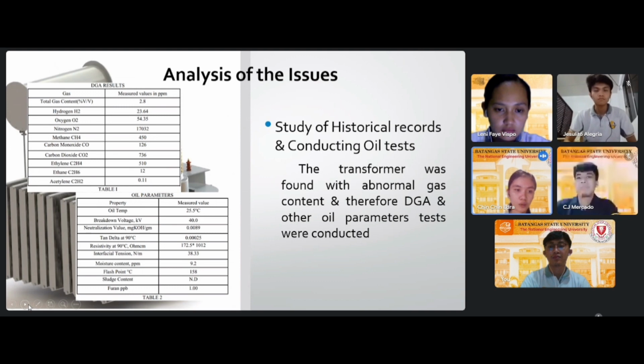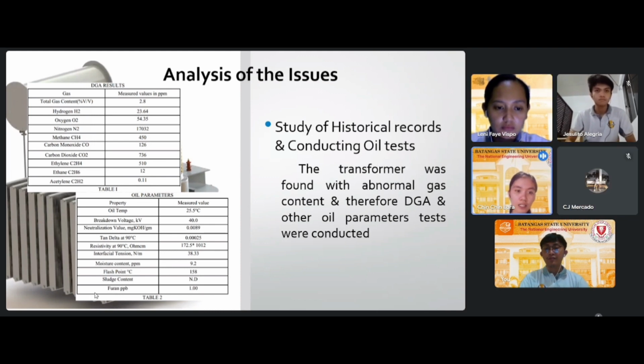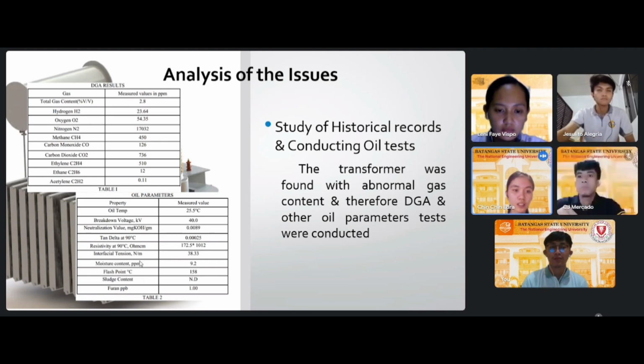For the result of oil parameters, the oil temperature has a measured value of 25.5 degrees Celsius. The breakdown voltage has 40. Neutralization value has 0.0089. The tan delta at 90 degrees Celsius has 0.00025. The resistivity at 90 degrees Celsius has 172.5 times 10^12. The interfacial tension has a measured value of 38.33. The moisture content has 9.2. Flash point has 158 and the furan has 1.